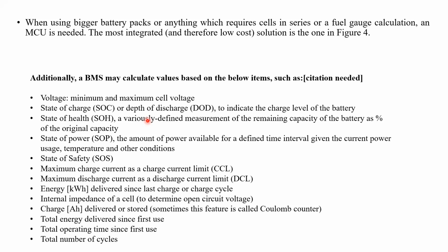Depth of discharge is whenever the battery charging level decreases beyond some particular level. For example, if the depth of discharge limit is 10%, and the battery decreases to only 10% charge, if we keep using the battery below 10%, the battery is going to be damaged and its lifetime will decrease.